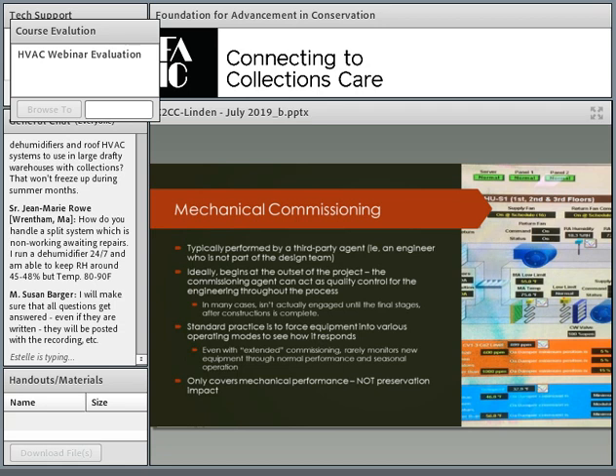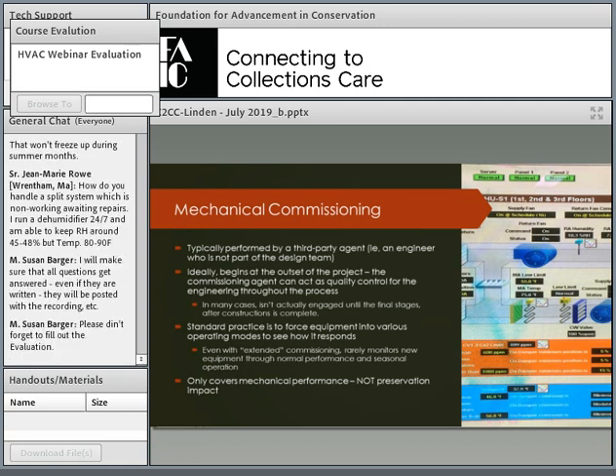More often than not, in real life the commissioning agent really gets engaged right about the construction stage, and most of their work is done after construction is complete. They're the ones coming into the mechanical system, looking at what the design intent was, in other words what's in the actual design drawings, and forcing the system into different modes of operation.